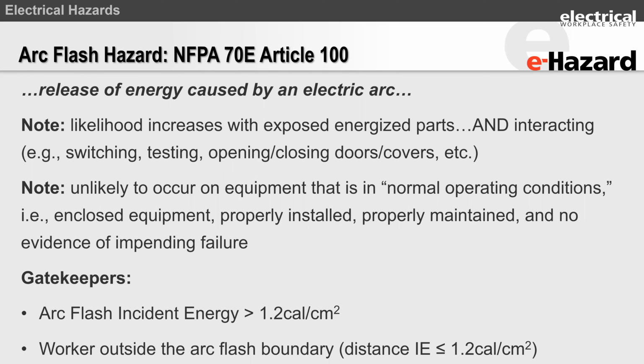The magnitude of the arc flash hazard can be substantial, or marginal, or one that cannot cause any harm. The other instance in which an arc flash hazard exists is when we are interacting with equipment: switching, testing, opening and closing doors and covers. I included switching specifically because one of the big risks we see in industry at the moment is that machine operators and plant operators who are not considered electrically qualified, people who have not received electrical training, are expected to switch on and switch off electrical equipment. Many consultants and industry experts will tell you that some of these machines have sufficient arc flash incident energy to ignite non-arc rated clothing. So that's one area that requires a little focus, to make sure nothing is slipping through the cracks.